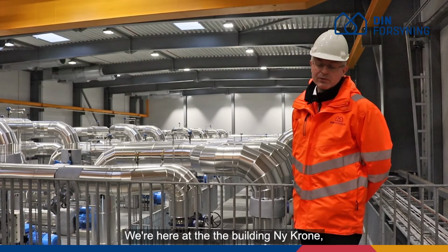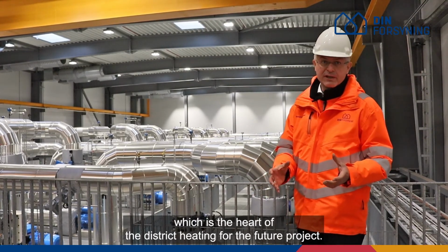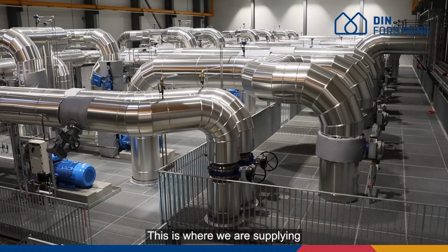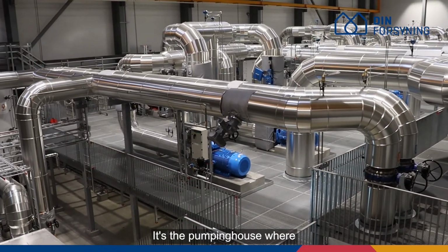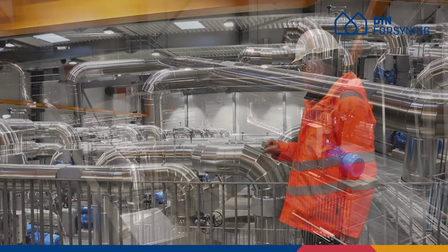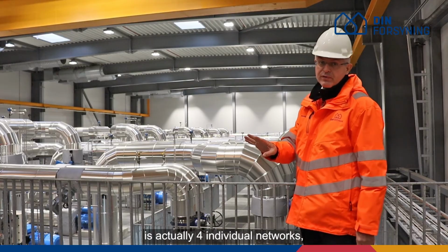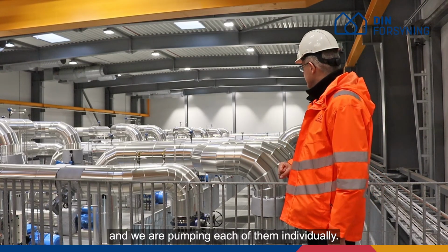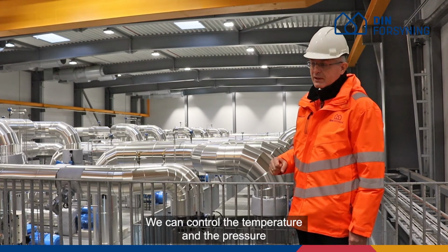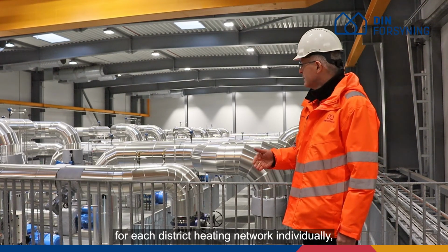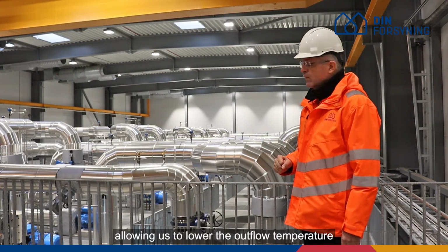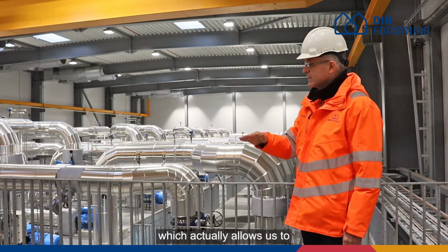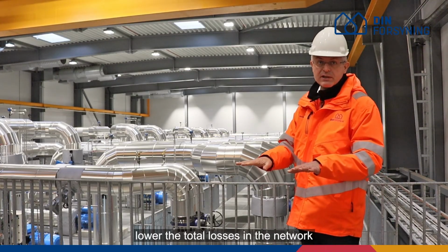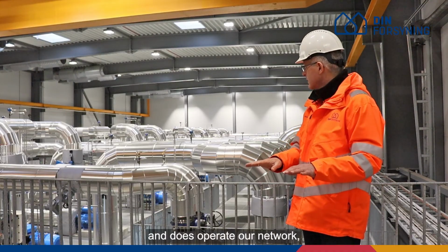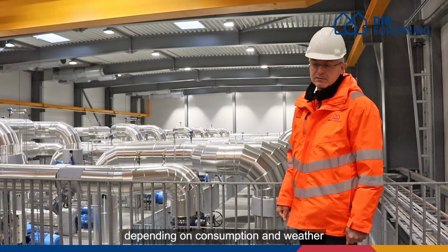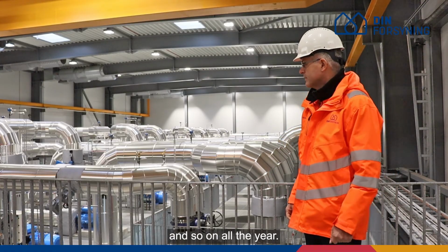We are here at the building Ny Krone, which is the heart of district heating for the future. This is where we are supplying the district heating to our customers. It's the pumping house where we have our distribution pumps. The district heating network in Esbjerg is actually four individual networks, and we are pumping each of them individually. We can control the temperature and the pressure for each district heating network individually, allowing us to lower the outflow temperature and increase the flow individually, which actually allows us to lower the total losses in the network and thus operate our network at optimal conditions depending on consumption and weather and so on all the year.